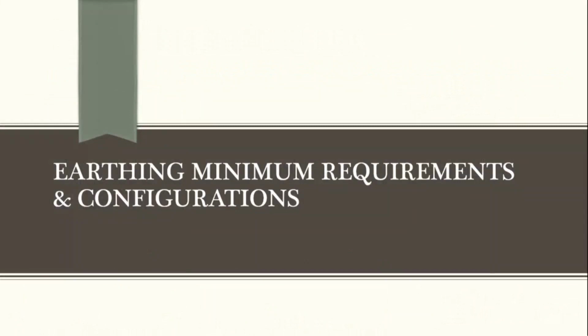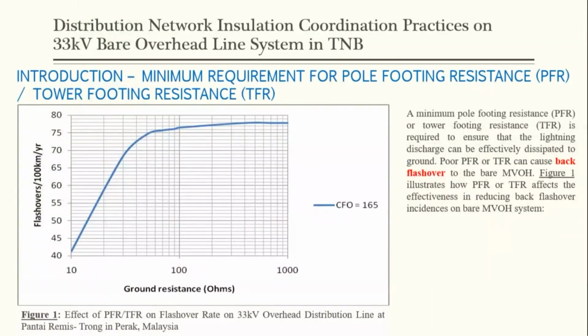Okay, the most important aspect in insulation coordination is the earthing minimum requirements and configuration, because we need to ensure that the lightning current can be dissipated to ground effectively. Okay, a minimum pole footing resistance or tower footing resistance is required to ensure that the lightning discharge can be effectively dissipated to ground. Poor pole footing resistance or tower footing resistance can cause back flashover to the bare medium voltage overhead line.